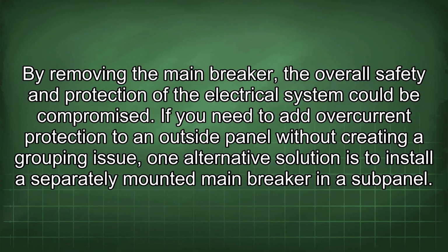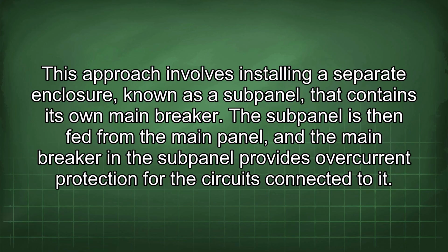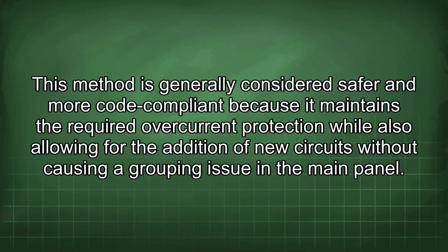If you need to add overcurrent protection to an outside panel without creating a grouping issue, one alternative solution is to install a separately mounted main breaker in a subpanel. This approach involves installing a separate enclosure, known as a subpanel, that contains its own main breaker. The subpanel is then fed from the main panel, and the main breaker in the subpanel provides overcurrent protection for the circuits connected to it. This method is generally considered safer and more code compliant because it maintains the required overcurrent protection while also allowing for the addition of new circuits without causing a grouping issue in the main panel.